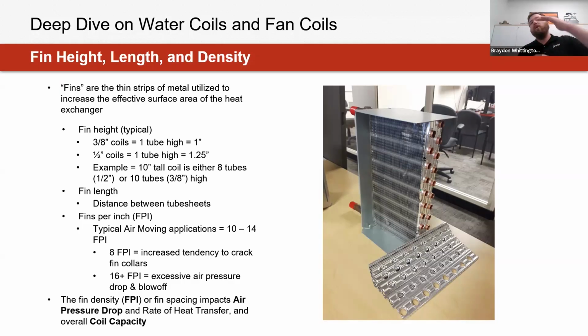That actually has an influence on what the overall fin height of that coil can be. The reason is that, based off the overall tube height or tube thicknesses used in that coil, we want to make sure the passes going through that coil always leave on the same side. We don't want the entry point on one side and the leaving point on the other. So with these coils, there are going to be restrictions on the overall fin height, or on the increments you can do for the height of a coil, because we want the entry point and the leaving point to be on the same side.